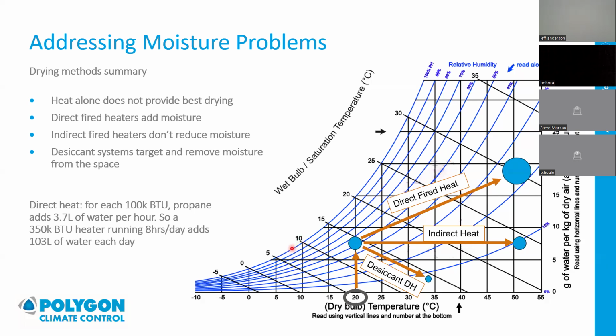It's just going to follow this line down until it can't cool anymore, then it's going to reheat it, and you end up drier and maybe a little colder. So it's this kind of C-shaped direction for refrigerant-based dehumidification. But our system really is just dry the air out, push it into a building, and force the moisture out. If the materials are already dry, say a site built 20 years ago that's just redoing the flooring, it's easier. We use smaller equipment, monitor the space, and automate the equipment to maintain whatever relative humidity levels they want.